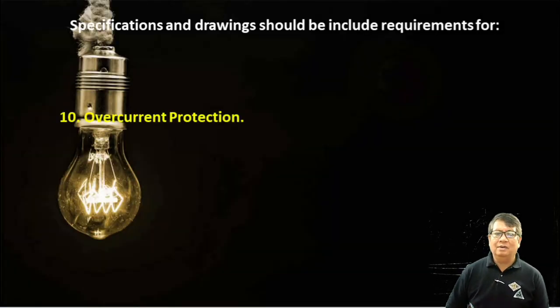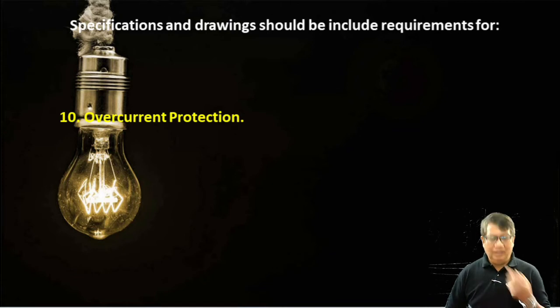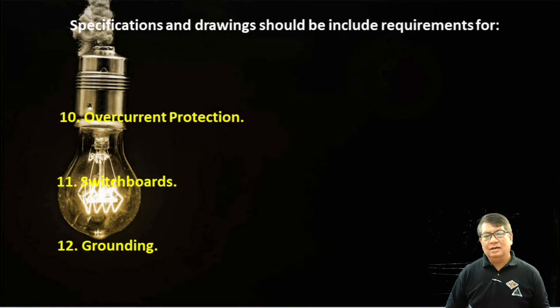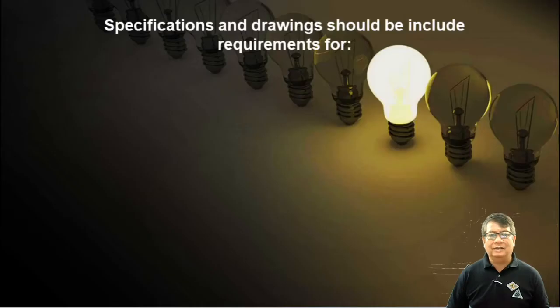Number 10, we have overcurrent protection. So actually, we have these two types of OCP, overcurrent protection devices: the fuses and the circuit breakers, no? So switchboards. Okay, this is a cabinet that includes protection all over the circuit. Now we have that switchboards. And it also specifies the grounding system in the building. So this is very important. Grounding system is very important. Okay, so this is to protect the whole installation.